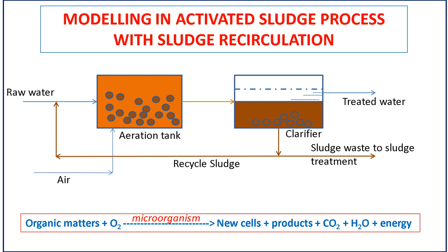The sediment from the bottom of the sedimentation tank contains a high concentration of microbes, which is then recirculated into the aeration tank. A portion of the sludge is also discharged to the sludge treatment unit to prevent accumulation of sludge solids, and also to adjust the residence time of microbial cells.